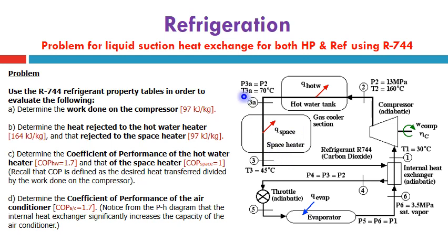Then the temperature T3A of the gas is reduced from 70 degrees to 45 degrees Celsius. We will note after this slide that the gas is above the critical point, so the temperature is pronounced here to be reduced from 160 to 70 to 45 degrees Celsius in the gas cooling system rather than condensation. There is no condensation process, but it is a heat removal process, and these gas cooler sections are in different sections.